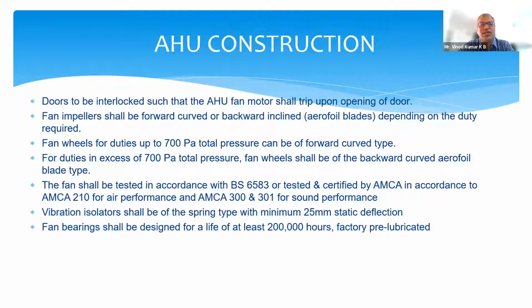So the AHU fan should switch off or trip when you open the door. In many places this cannot be seen because it's never been told to the vendor, and the vendor doesn't give it because it's a cost for him. So there is a tripping mechanism for the AHU fan motor when you open the door while it is functioning. When you switch off the AHU for maintenance, it's fine.